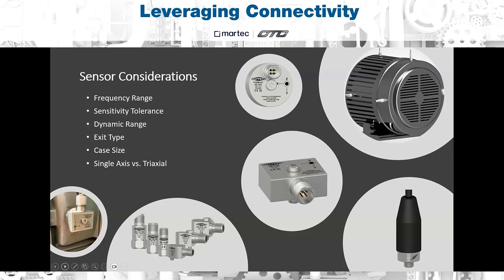And then regarding single axis or triaxial sensors, when possible, it's always best to monitor the vibration level in all three directions. Whether this is achieved using 3 single axis sensors or 1 triaxial sensor, there are many benefits and trade-offs to both. For permanent installations, the 3 separate single axis sensors provide the highest quality data. However, this requires 3 separate sensors, 3 separate mounting spaces, as well as 3 separate cables. So alternatively, you could also utilize a triaxial sensor, which would only require 1 of each. For portable measurement, however, utilizing a triaxial sensor can be far more efficient and save the vibration analyst time and money when taking your readings on your data collecting route.